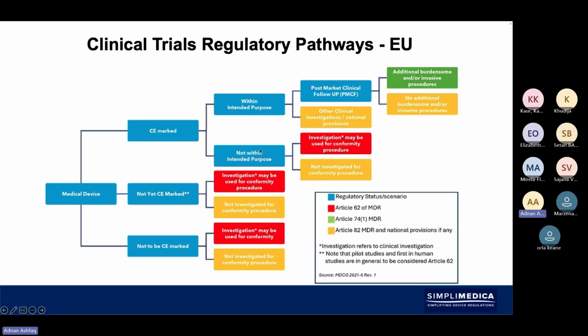What's not within the intended purpose. If you can simplify your claims and simplify your medical device, that's always a good strategy to use. Now, the other thing that you can also do is, if you had a device which had very extensive clinical claims, which makes your device a very novel device where there's no existing devices on the market, it's also possible to bring your device claims back, to simplify your device just to get it into the market with a simple intended purpose.